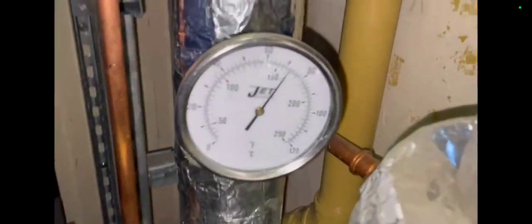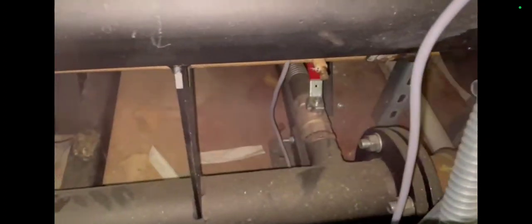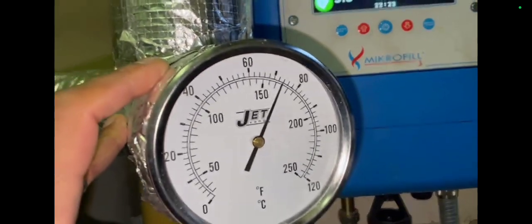So I put marks on my plate-to-plate to identify what pipes are doing what. And I'm just tracing the pipe work to look for the restriction. I believe the restriction was on a strainer, but that isn't a five-minute job, depending on whether I have gaskets and so on or not, and if the isolation valves actually hold up.